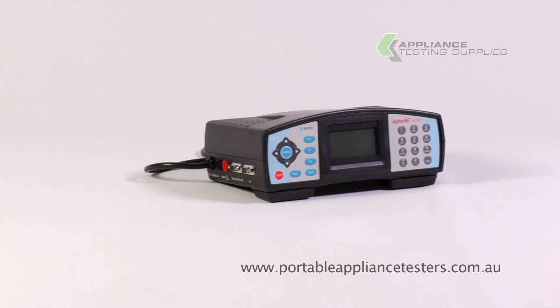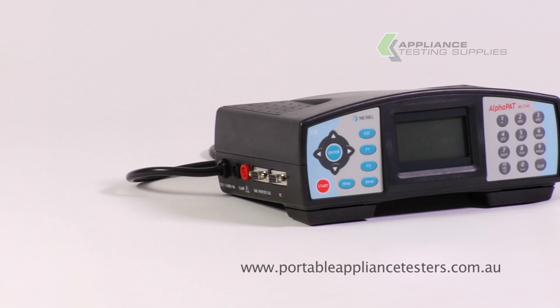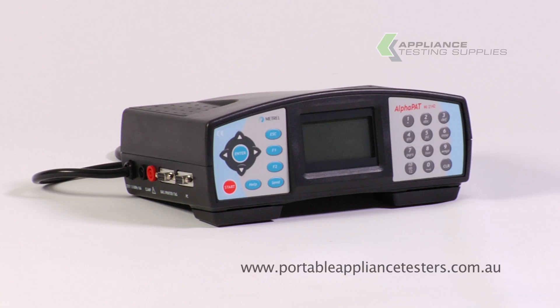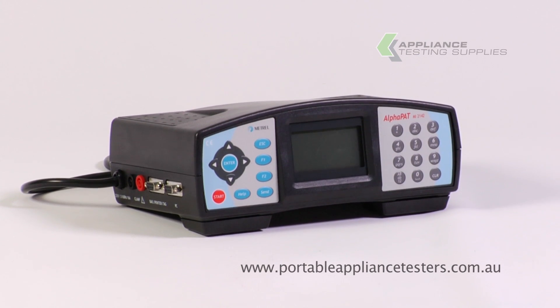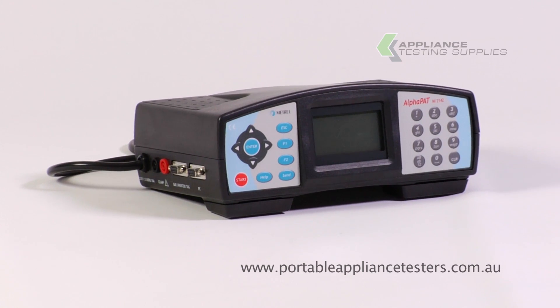The Metrel AlphaPAT. This is a high spec unit which has download capabilities. A clamp meter can be used in conjunction with this unit to test three phase. It has selectable earth bond testing from 100 milliamps through to 25 amps. It can also be connected to a printer and scanner, and you can program this unit to customize your testing.